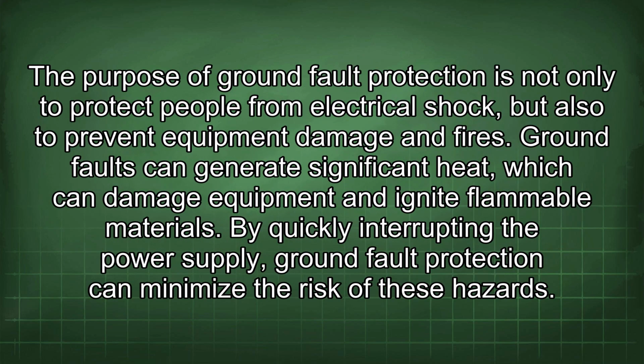The purpose of ground fault protection is not only to protect people from electrical shock, but also to prevent equipment damage and fires. Ground faults can generate significant heat, which can damage equipment and ignite flammable materials. By quickly interrupting the power supply, ground fault protection can minimize the risk of these hazards.